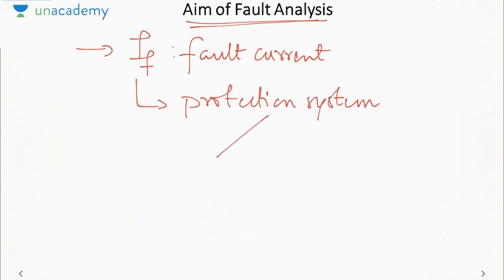Now protection system has two parts. One is called protective relays, other is your circuit breaker. Now the working of relay is, it has to sense the abnormal condition, then inform the circuit breaker that there is abnormal condition in the circuit, so the circuit breaker can open circuit the power system. So relay must only sense. Now if I give you two currents, one is the minimum fault current, other is the maximum fault current, which current should the relay operate on? The answer is, it must always operate on minimum fault current, because if it can detect that 100 ampere is an abnormal condition, then definitely 200 ampere will also be an abnormal condition for the relay. But if you set 500 ampere as the abnormal condition, whereas the fault current is 100 ampere, it will think that 100 ampere is a normal current, there is no fault in the system. So fault will not be cleared.